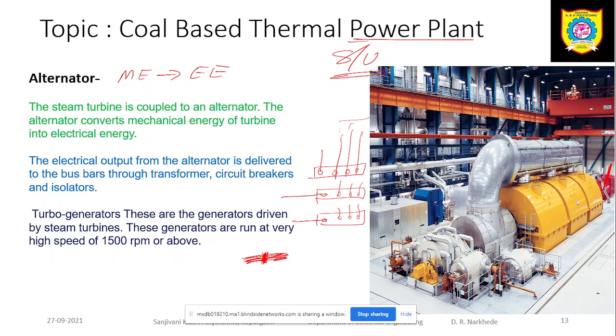Basically, if I am going to generate the electricity, there are certain constraints because of which I cannot generate the electricity at a very high voltage. So the electrical energy generated at the power plant may be 1.1 kV to 11 kV. Or normally we generate the energy at 11 kV. And the size of that power plant may be 100 megawatt or like this.